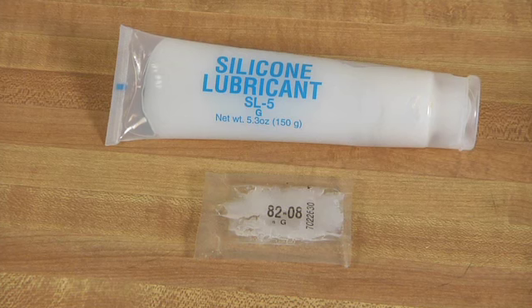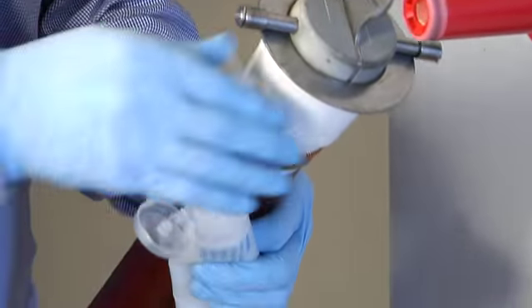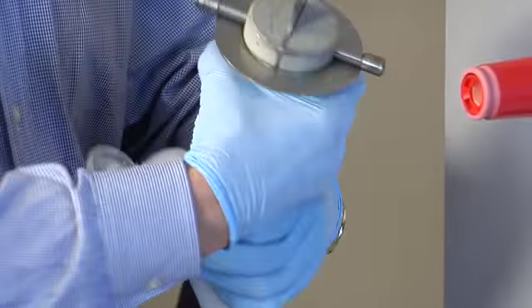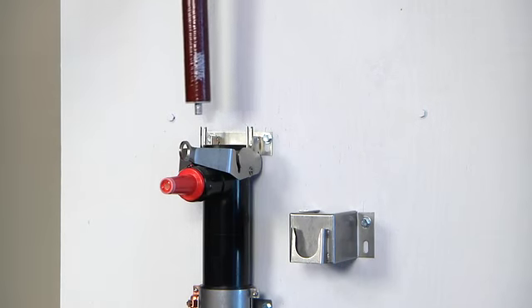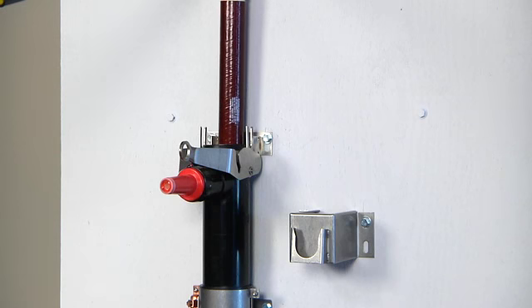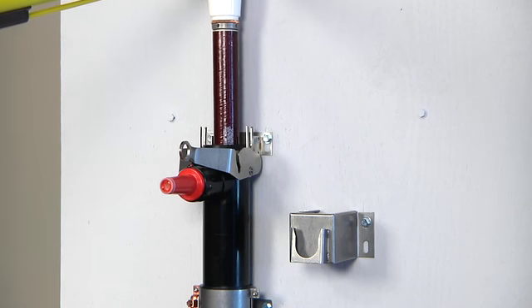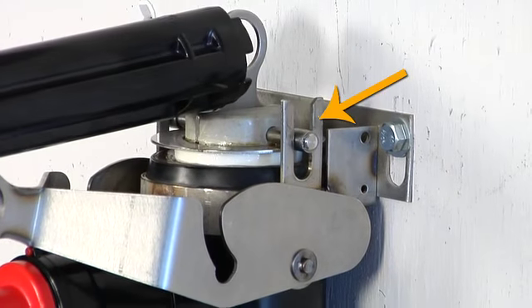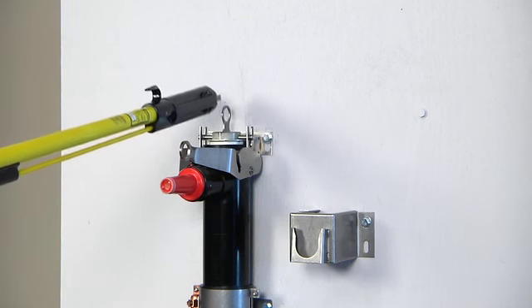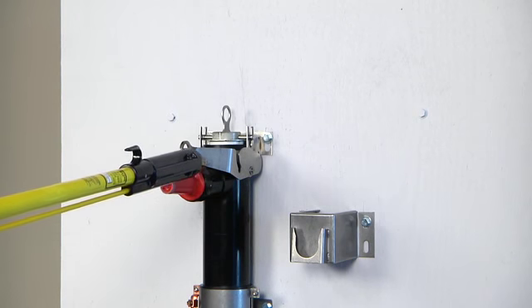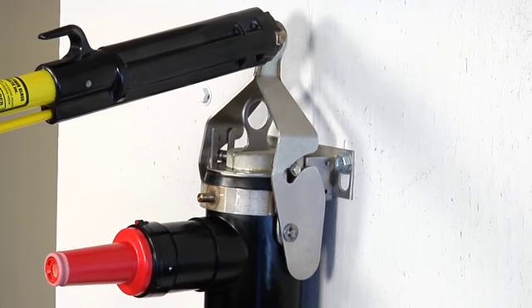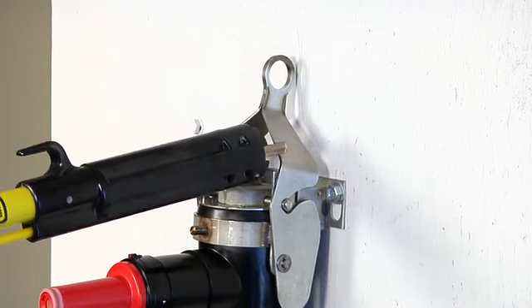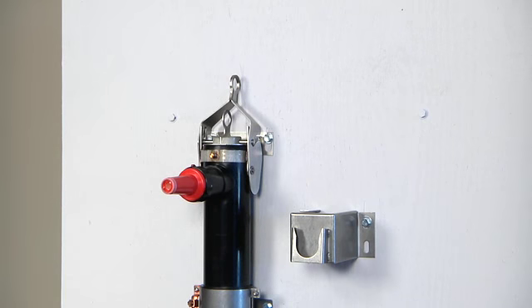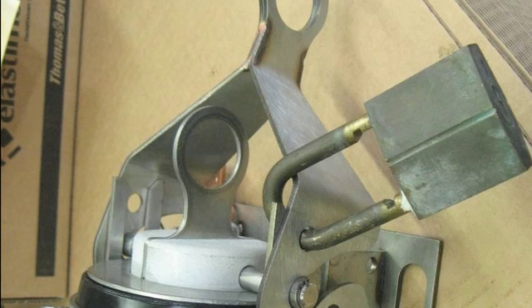Lubricate the end plug surface with the supplied lubricant. Do not substitute. Guide the fuse into the canister opening. Then, slide the fuse into the canister, ensuring that the guide rod enters the fork. Next, engage the canister lever eye with the hook stick. Push the lever close to the canister. The guide rod will click into the lever arm dent when fully seated. Finally, insert the locking pin or install padlock to secure the lever.